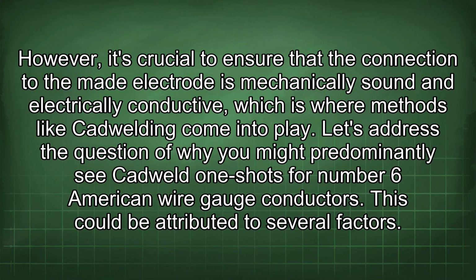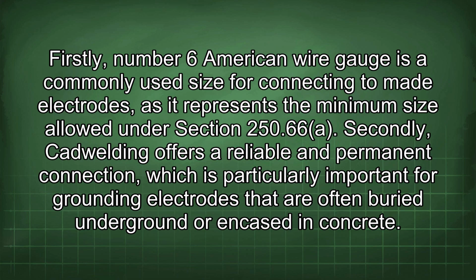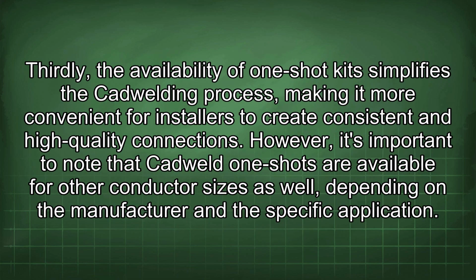Let's address the question of why you might predominantly see Cadweld one-shots for number 6 American wire gauge conductors. This could be attributed to several factors. Firstly, number 6 American wire gauge is a commonly used size for connecting to made electrodes, as it represents the minimum size allowed under Section 250.66. Secondly, Cadwelding offers a reliable and permanent connection, which is particularly important for grounding electrodes that are often buried underground or encased in concrete. Thirdly, the availability of one-shot kits simplifies the Cadwelding process, making it more convenient for installers to create consistent and high-quality connections. However, it's important to note that Cadweld one-shots are available for other conductor sizes as well, depending on the manufacturer and the specific application.